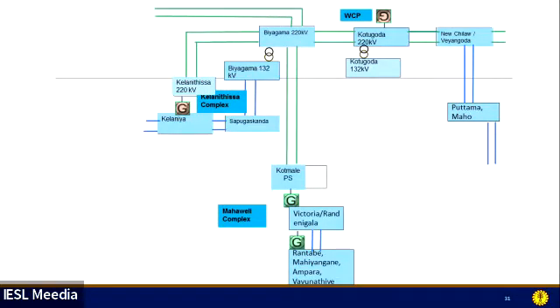Initially, the Mahaweli system started to restore. Then the Kotmale system restoration got delayed because of an energization delay due to the Kotmale Biyagama 2 lines. So we went to the Victoria side. We energized the Rantembe and Ampara substations initially. Then, after recovering the two transmission lines, Kotmale Biyagama, we restored Kotmale. Then we synchronized the two systems at 15 hours.